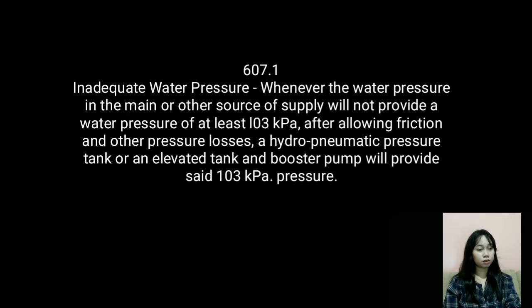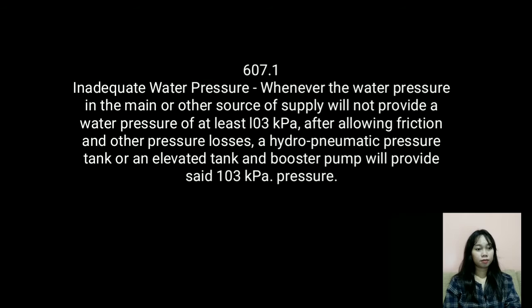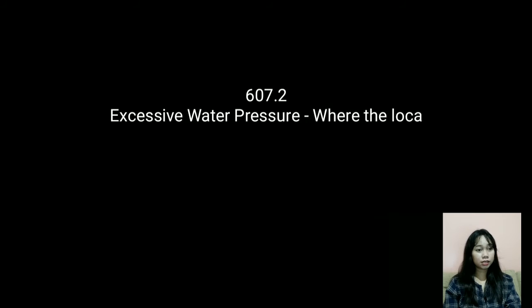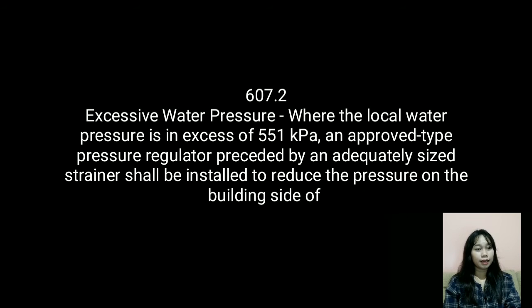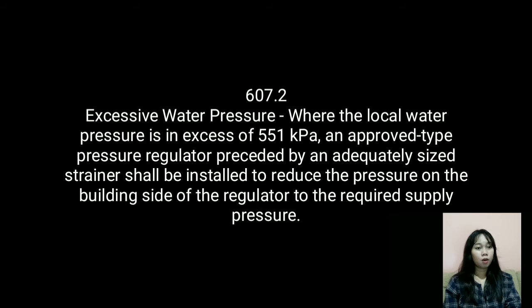In Section 607.1, regarding inadequate water pressure — whenever the water pressure in the main or other source of supply will not provide a water pressure of at least 103 kPa after allowing for friction and other pressure losses, a hydropneumatic pressure tank, or an elevated tank and booster pump, shall be provided to supply the required 103 kPa pressure.